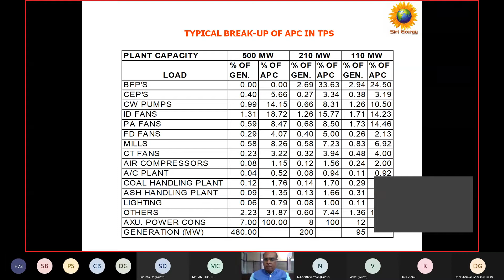So same thing, whatever I showed earlier, it is in percentage. You can see APC means auxiliary power consumption for a typical 210 megawatt plant. Nowadays, in supercritical boilers or super thermal boilers, the boiler feed water pump is operated by the steam turbine. That's why their auxiliary consumption reduces. But of course, this will reduce overall efficiency of the cycle because we are taking some part.